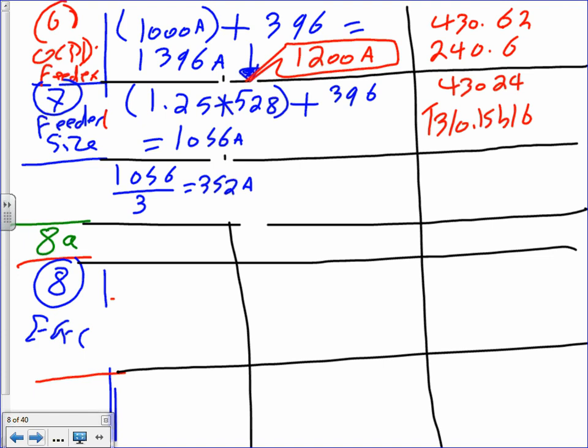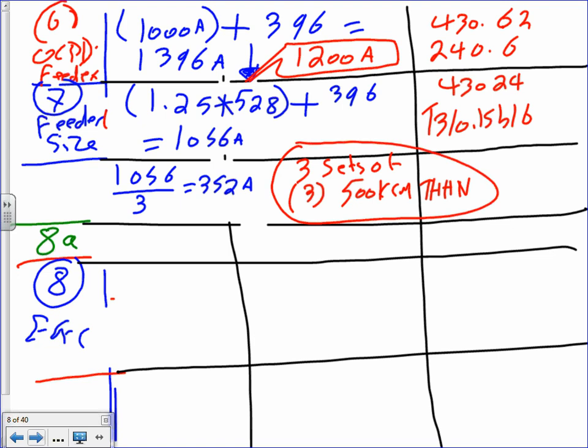Then, we all know, you need three sets now, three sets of three conductors. Each one of them is 500 kcmil THHN. So that's the size of your branch circuit. The size of branch circuit, three sets of three. Why do we always say three with motors? We don't even think about the neutral. No neutral. That's the beauty of running a three-phase motor, guys. Three conductors, done. That's why we run three-phase motors, no neutral.